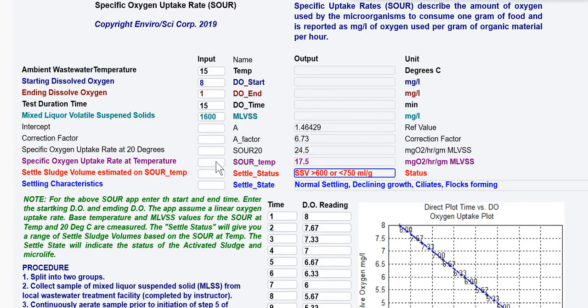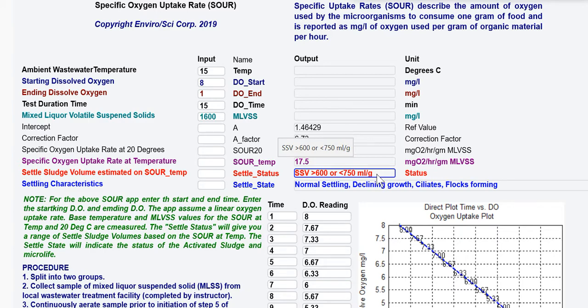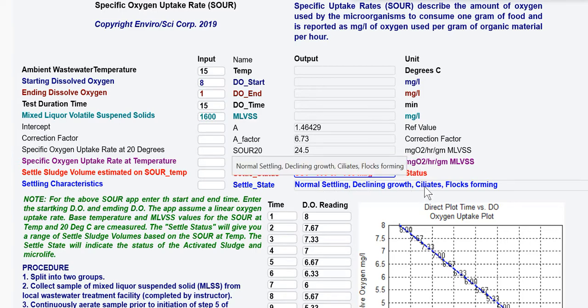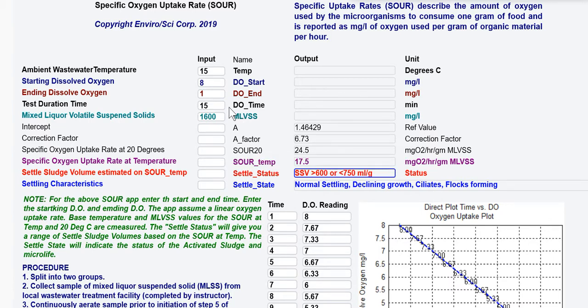Based on the SOUR at temperature, the application indicates what the settling status would be like. In this case the settled sludge volume would be between 600 and 750 milliliters per gram. Settling characteristics give you what you might anticipate in terms of who's home for the bacteria — in this case: normal settling, declining growth, stalked ciliates, and floc-forming organisms.